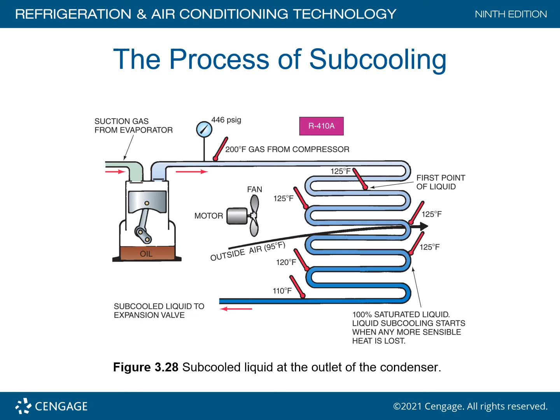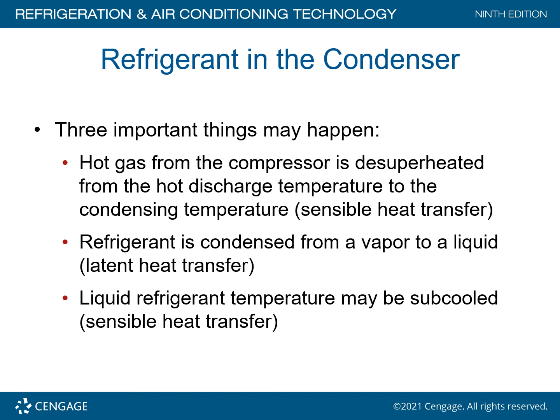Refrigerant in the condenser: three important things happen. Hot gas from the compressor is desuperheated from hot discharge temperature to the condensing temperature, a sensible heat transfer. Remember, sensible is the heat that you can measure and feel. Refrigerant is condensed from a vapor to a liquid, in this case hidden heat. Latent heat always refers to hidden heat, which you cannot measure. Liquid refrigerant temperature may then be subcooled. A sensible heat transfer process is employed in this.